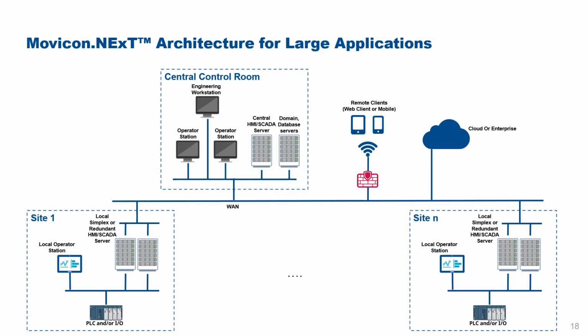If it's a few seconds or a few minutes old, it doesn't matter much, especially since you're often doing analysis over older legacy data anyway using the database. So your central control room might be coordinating using data from the databases, using some sort of reporting type application rather than a dedicated HMI SCADA application. So there are multiple options for these larger applications, but the architecture typically looks like this, with multiple distributed computers. Again, you have the option of redundancy, you can distribute your databases, and you can have multiple clients connected in multiple locations, with support for cloud and enterprise integration as well.